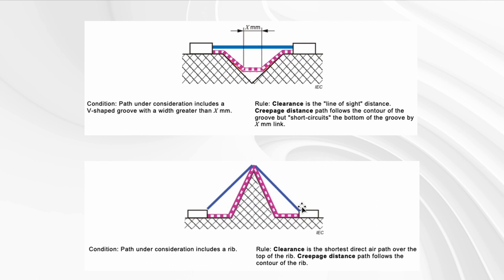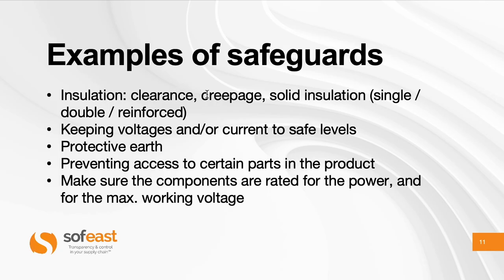Creepage follows the contour of the surface. If it's a V-shaped notch like this, creepage follows the contour of that shape, except when there's a short distance across the notch — then you calculate it across that gap. If it's another shape, it just goes all along the contour. So clearance and creepage are distinct measurements.